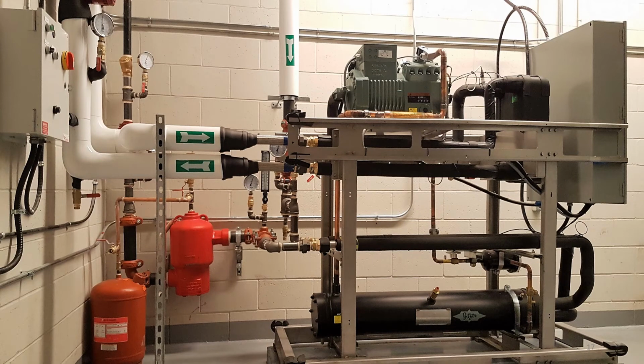Here is an example of a side stream chiller. In this case, the unit recovers heat for a single air handling unit. Chilled water connections are in the midsection and are connected to a large existing main chiller plant. Hot water connections are near the bottom as they're connected to the red air separator. The chiller runs and the compressors are controlled to the leaving condenser water temperature, which is the supply to the air handling unit. We are confident that there is a cooling load year-round, and therefore we will always have a source to recover heat from.